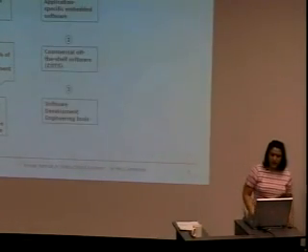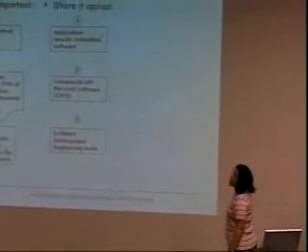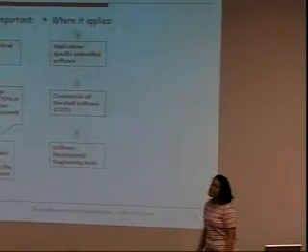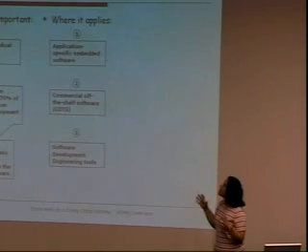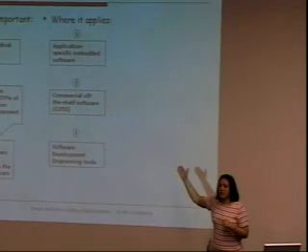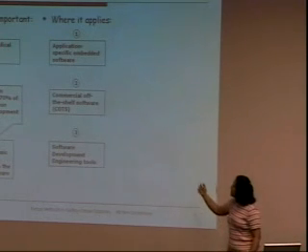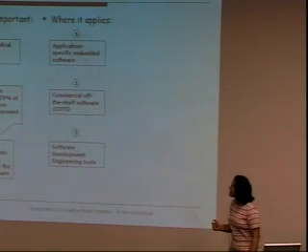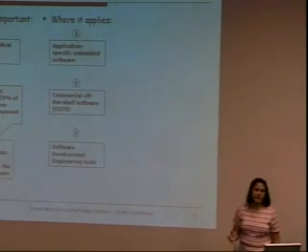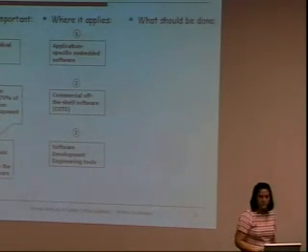Second, what kind of software does it apply to? In three kinds of software in general: the application-specific embedded software, the commercial off-the-shelf software, or those libraries that exist and can be used in software medical devices, and finally, even the software development engineering tools like CASE tools. The risk analysis should be done.